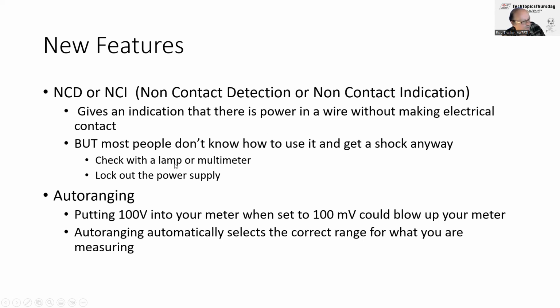If you're working on AC power like an electrical outlet, check with a lamp or a working multimeter just to make sure there's no voltage there. Then lock out the power supply, lock out the breaker or your shack power supply if you're working on it, just to make sure no one turns it back on again.